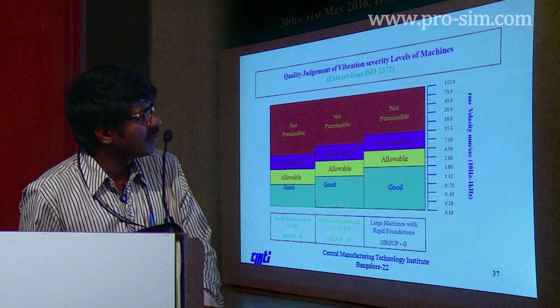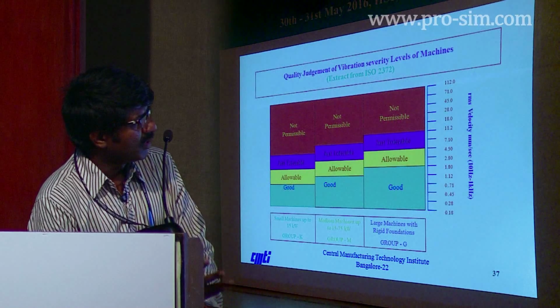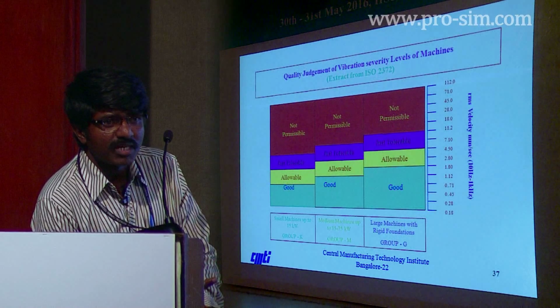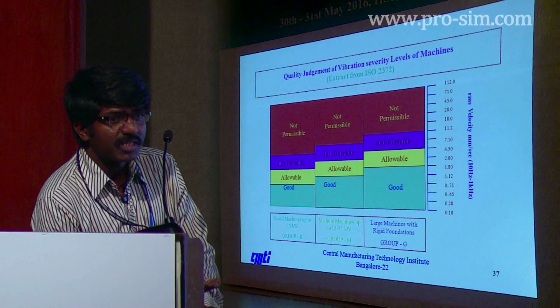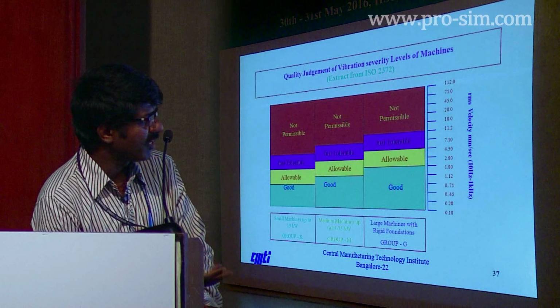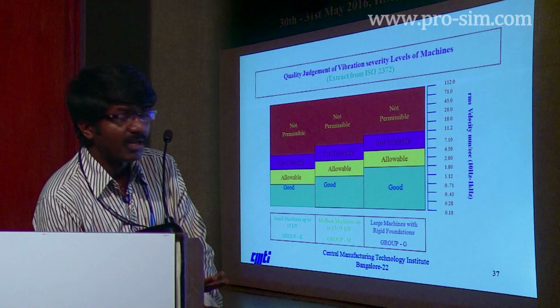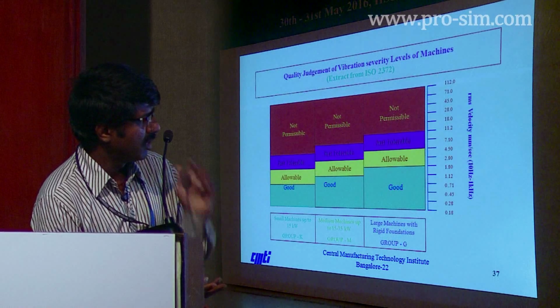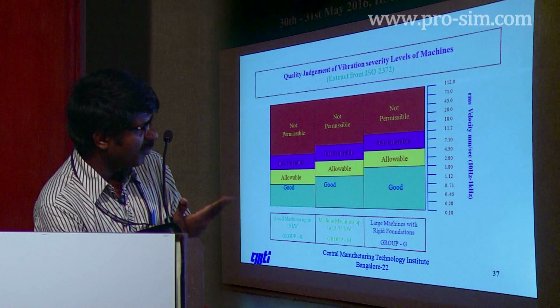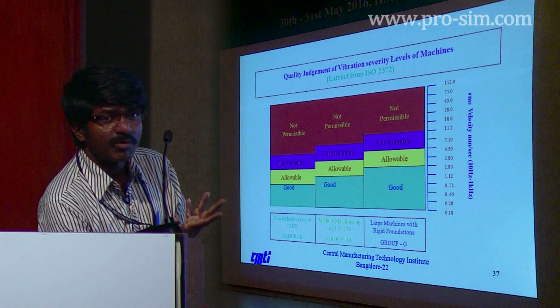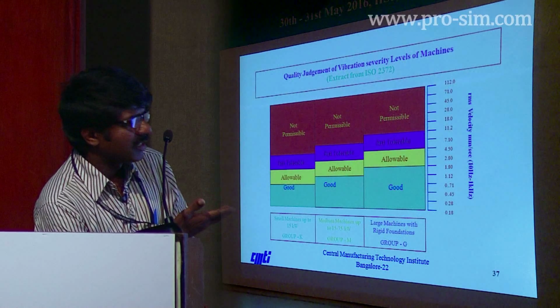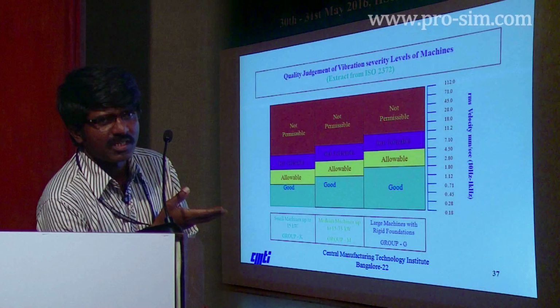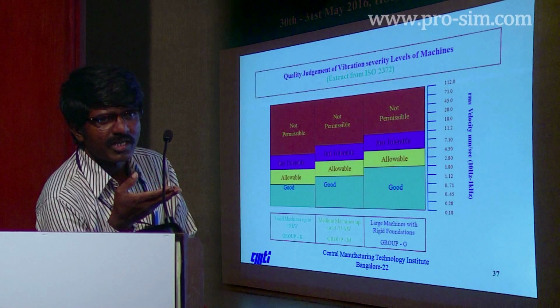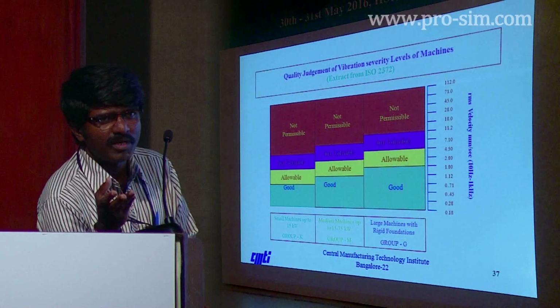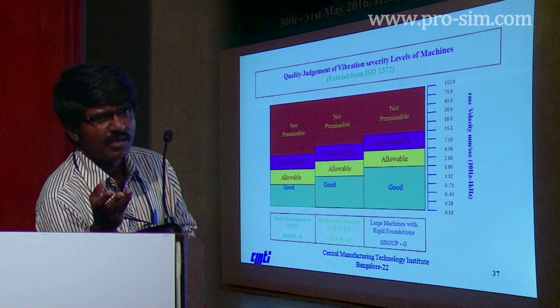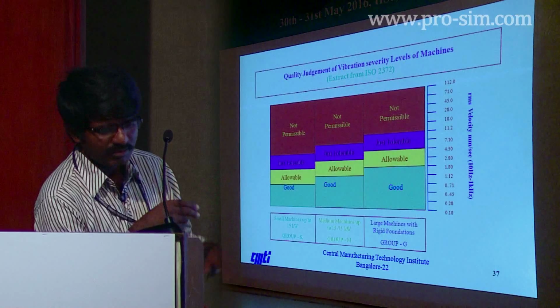Of course, you can use an ISO standard like 2372. If you want to fulfill some criteria, here machines are divided by power rating, like up to 15 kilowatts, 15 to 75, and large machines mounted on rigid foundation. Good means, for example for 15 kilowatts, 0.71 millimeter per second of vibration you can allow. Okay. In this, it does not specify what type of machines and other things. If you are using very precision grinding machines, even 0.71 millimeter per second itself is abnormal vibration. They are not mentioned. These are all the drawbacks of this standard.